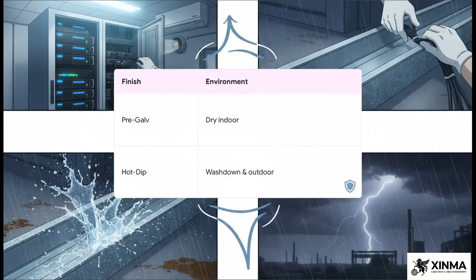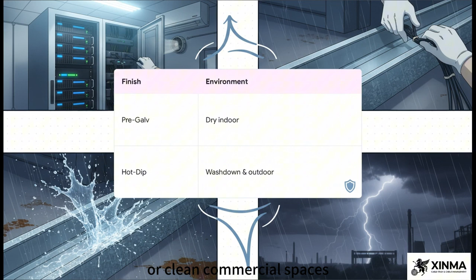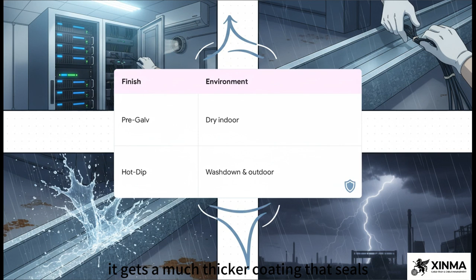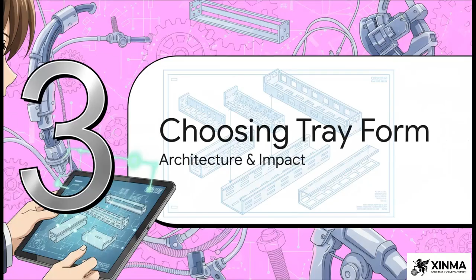So let's map this out clearly. Pre-galvanized steel belongs strictly indoors, think dry, climate-controlled data centers or clean commercial spaces. But if your facility has washdown-prone areas, or you're routing cables outdoors in industrial conditions, hot-dip galvanized is your absolute must-have shield. Because it goes into the zinc bath after fabrication, it gets a much thicker coating that seals every single cut and hole. It actually survives those harsh realities.